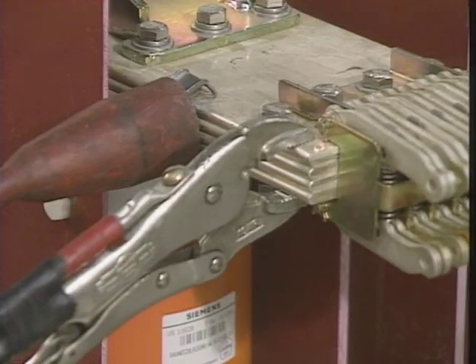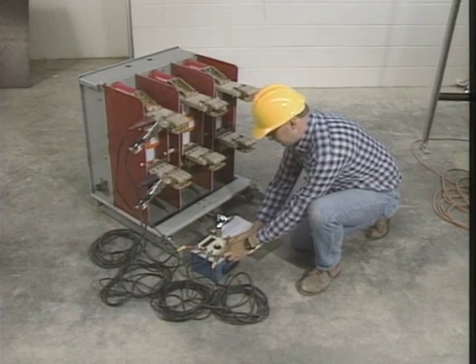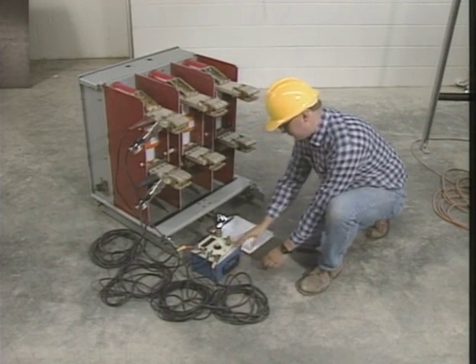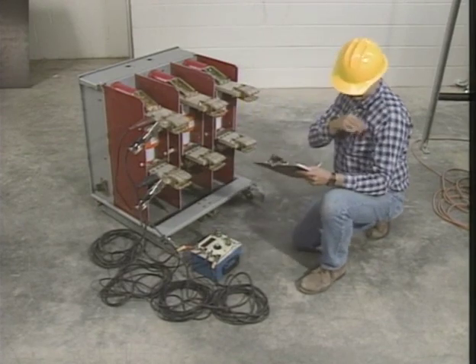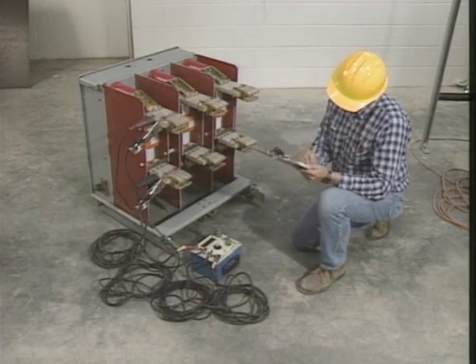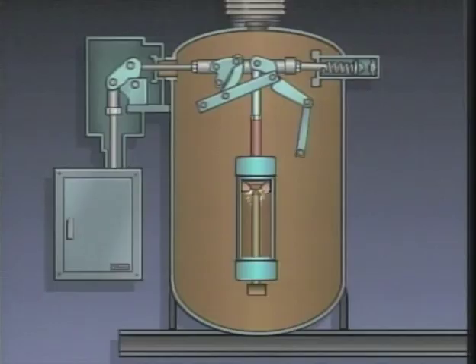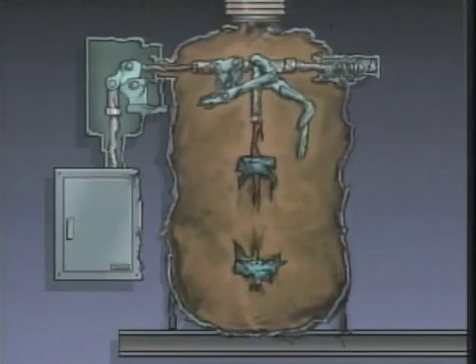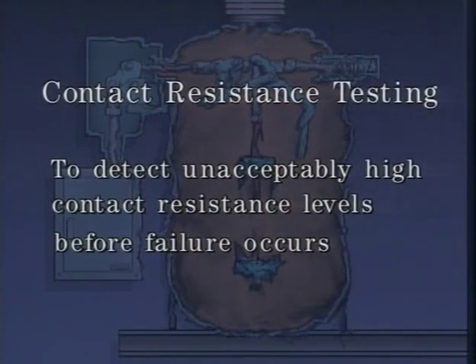Another proof test that's often recommended is the contact resistance test. Resistance in the closed contacts of a circuit breaker can have a number of causes, including arcing deposits, a loose or incomplete connection, or pitting from repetitive arcing. Contact resistance creates heat that can reduce the life of the contacts and may even lead to breaker failure. The purpose of contact resistance testing is to detect unacceptably high contact resistance levels before failure occurs.